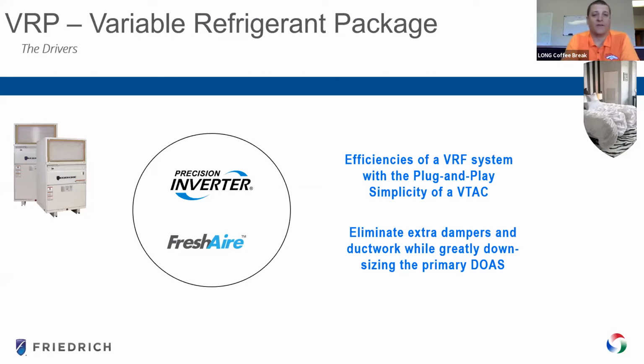So Friedrich just developed their VRP unit, trying to come up with a way to pair the VRF technology, which is newer technology where we're better able to match part load to the conditions you're seeing in your space, while still maintaining a modular install approach that minimizes the amount of outside air, ductwork, dampers, and penetrations that you have to have. So in doing that, they were able to come up with the VRP unit, which also is able to introduce outside air to the space when you need it while the unit is running.